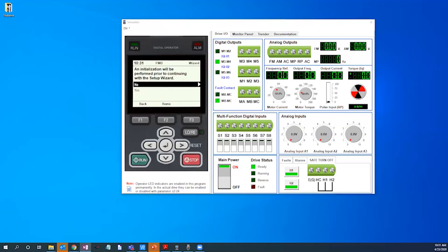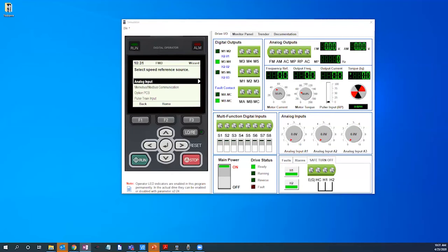We will then select yes for initializing prior to setup wizard. Now we are ready to begin initialization. We will select analog input for speed reference 0 to 10 volt input signal and here we will press enter as the analog signal is already virtually connected.